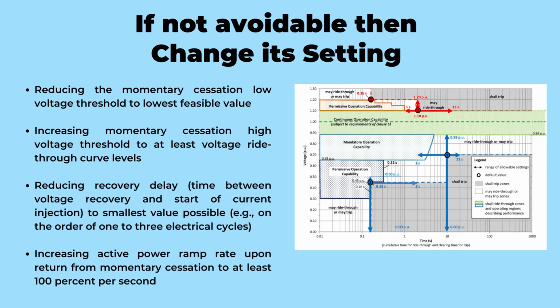If completely eliminating momentary cessation is not feasible, the next question arises: can we modify its settings to optimize its functionality? Let's find out. Thankfully, there are measures that can be deployed as features in these inverters to improve their performance. Let's take a closer look at some of these strategies. First is reducing the low voltage threshold for momentary cessation. By setting the threshold to the lowest feasible value, we can ensure that the inverter responds more effectively to voltage fluctuations, even at low levels. Second is increasing the high voltage threshold for momentary cessation. Setting the high voltage threshold to at least the voltage ride-through curve levels enables the inverter to withstand higher voltage surges, enhancing its resilience during power disturbances. Third is reducing the recovery delay. The recovery delay refers to the time interval between voltage recovery and the resumption of current injection. By minimizing this delay to the smallest value possible, for example, on the order of 1 to 3 electrical cycles, the inverter can swiftly restore its operations, minimizing disruptions to the power system.